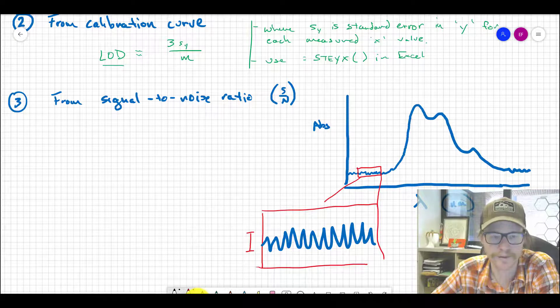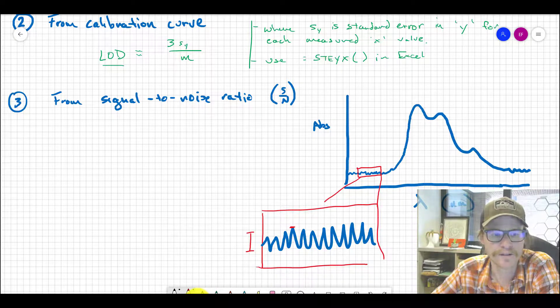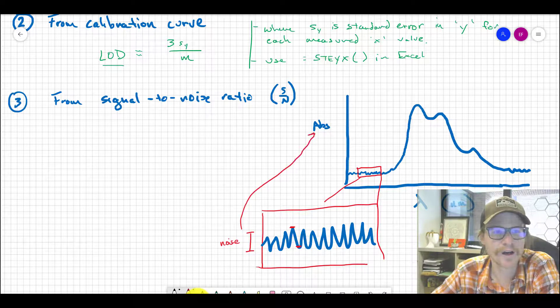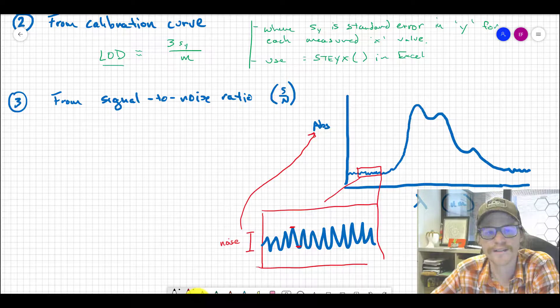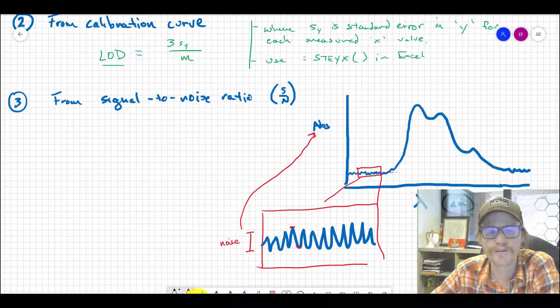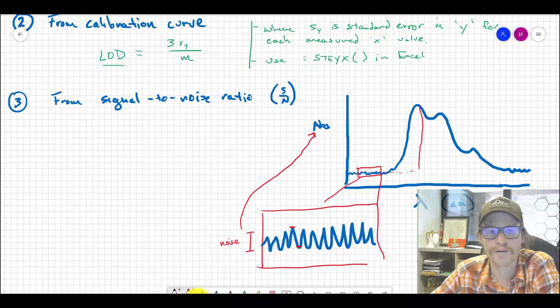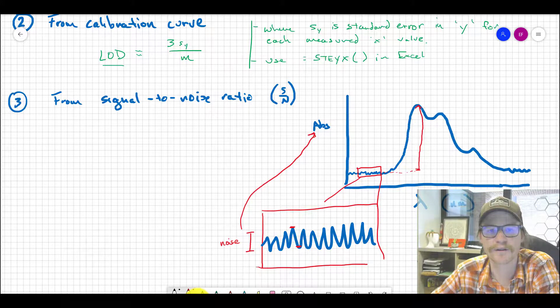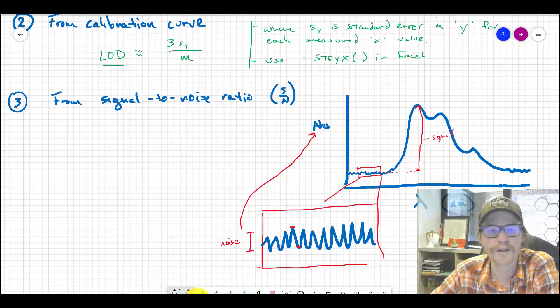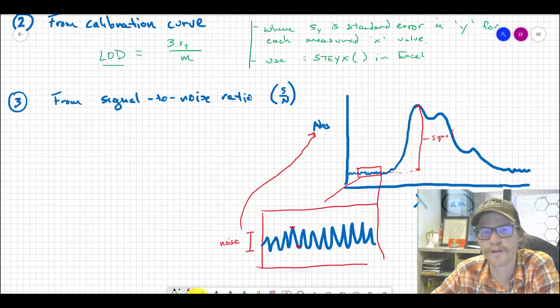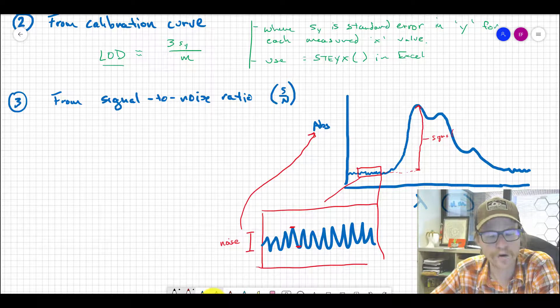From the peak to the trough—that's the noise measured in our response units, absorbance, on the y-scale. The signal would be from the centroid of that baseline all the way up to wherever the maximum signal is for our analyte. If you take the signal in absorbance units divided by the noise, that's the signal-to-noise ratio.